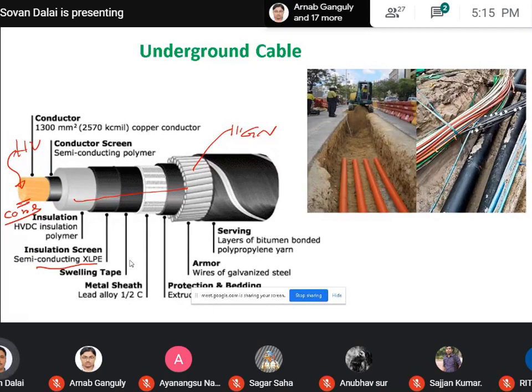So capacitance is more in the case of underground cable, so it basically draws a larger amount of charging current for charging the capacitor. This is one of the limitations of the underground cable. Underground cable is also designed for a few hundred kilovolt, 132 kilovolt, 66 kilovolt, in that range.